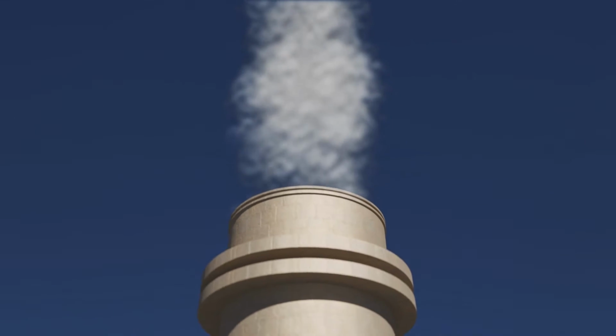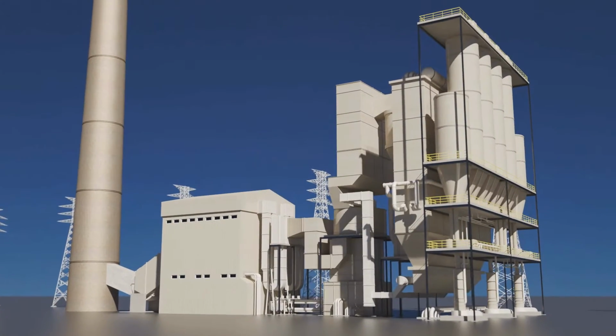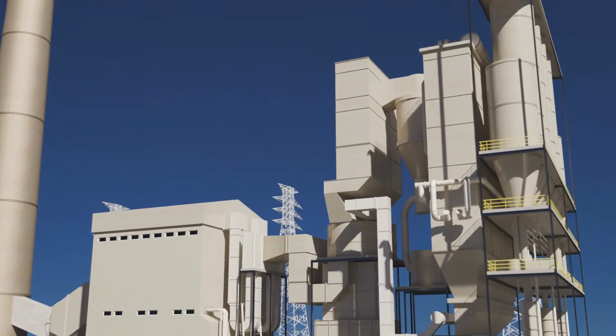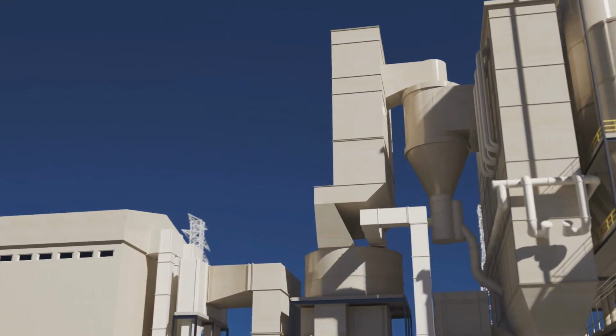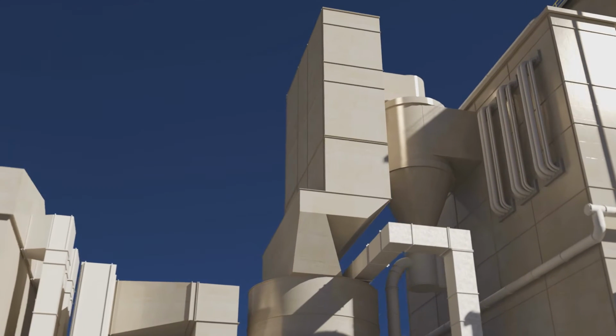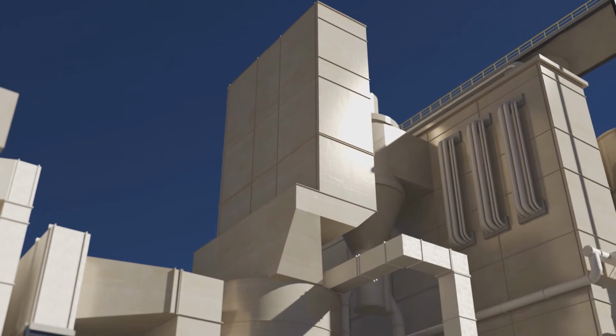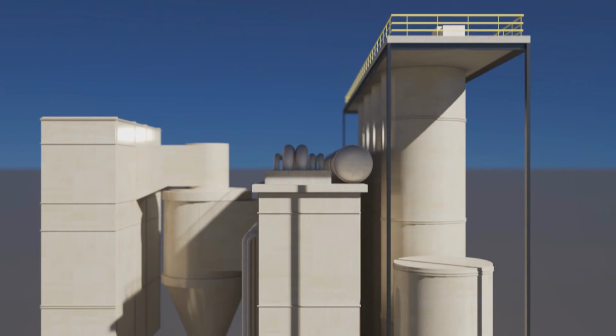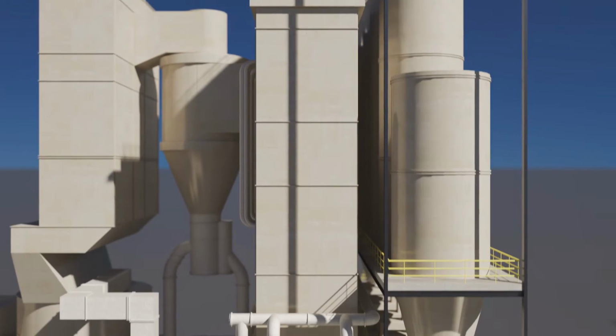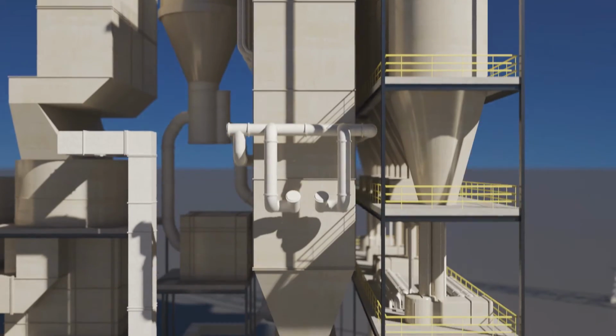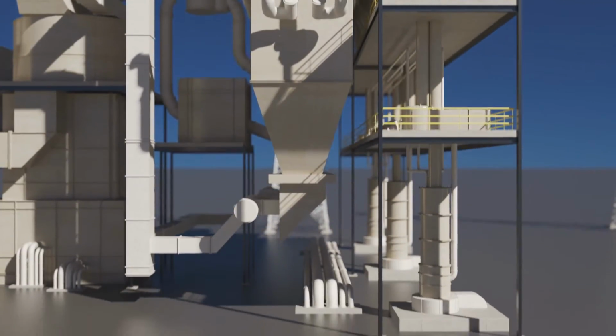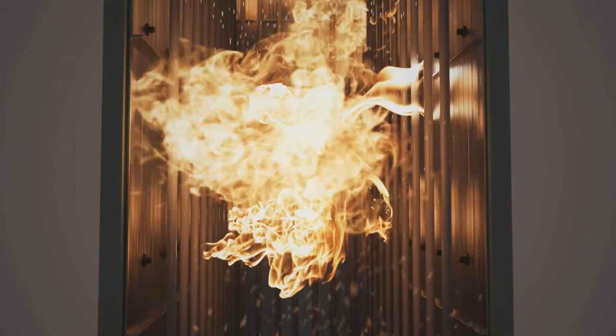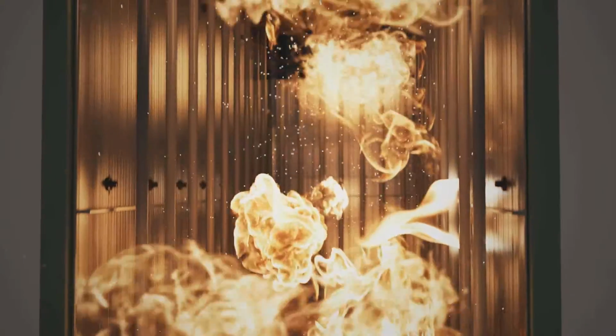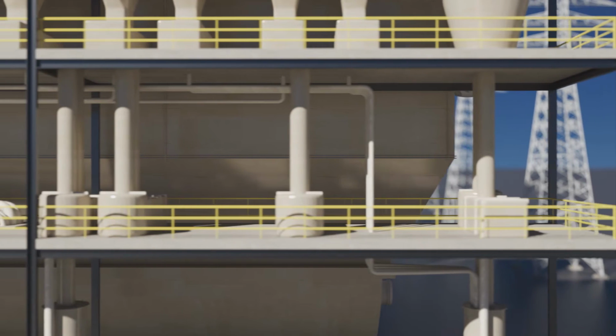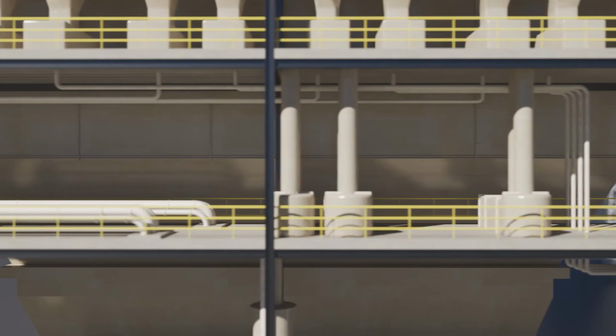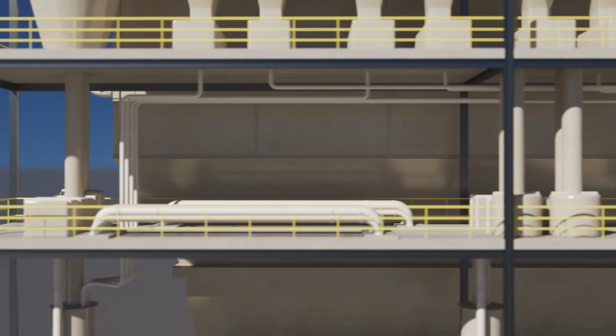Notice that there is no scrubber in the CFB process. Why? Because with CFB technology, a scrubber isn't necessary. Remember how the coal is mixed with the limestone in the boiler? That ground limestone reacts with the gas in the combustion chamber and captures up to 98% of the sulfur dioxide. And since the unit operates at about 1,600 degrees, much lower temperatures than the pulverized coal units, the amount of nitrogen oxide created is negligible.